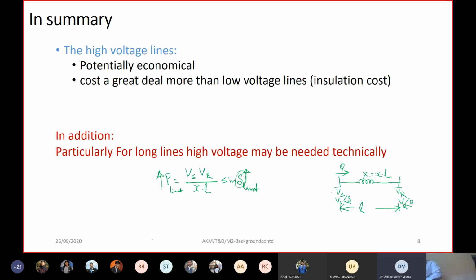I'd like to clear up a confusion here. When we say the phase angle difference limitation for transient stability is 30 degrees, this does not mean that if the phase angle difference between two buses in the power system is 35 degrees, the system will go unstable. No, that's not what it means. It means that the lower the phase angle, the higher the probability of the system remaining in synchronization even after a big disturbance.